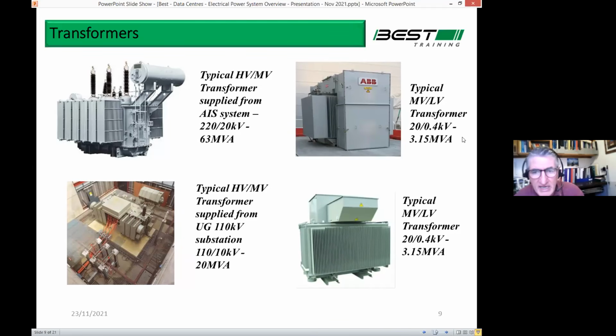The two on the right are MV to LV, transforming from 20 kV or 10 kV down to 400 volts. 400/230 is the standard voltage we use in commercial and industrial buildings. In your house, as you know, it's 230 volts single phase, but in industrial and commercial buildings they use 3-phase, and it's 400/230. So that's what these transformers transform it down to, the final safe voltage that you can distribute around the building. The top one is typically about 3 megawatts capacity, and the one down the bottom says 3 megawatts. That's a copy and paste error. It should be probably about 1 megawatt or 1.6 MVA, whatever.